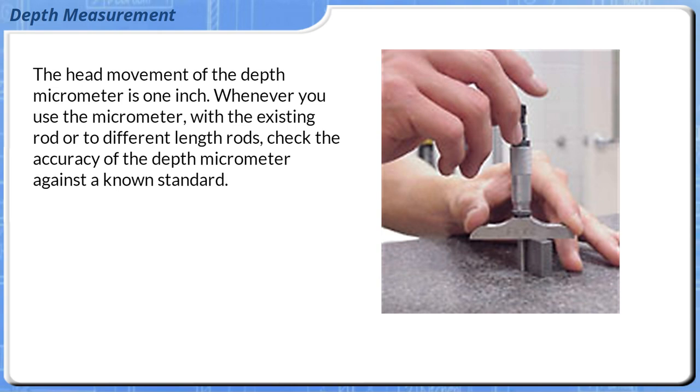The head movement of the depth micrometer is 1 inch. Whenever you use the micrometer, with the existing rod or different length rods, check the accuracy of the depth micrometer against a known standard.